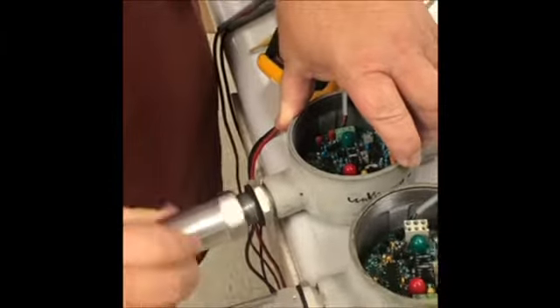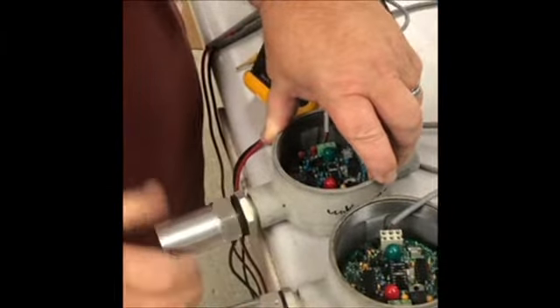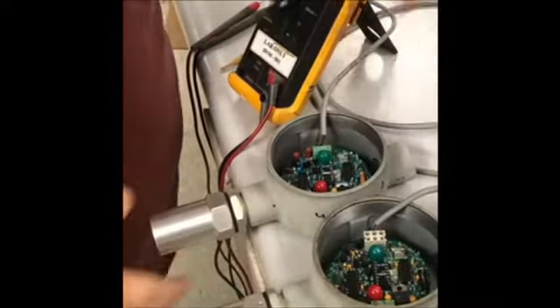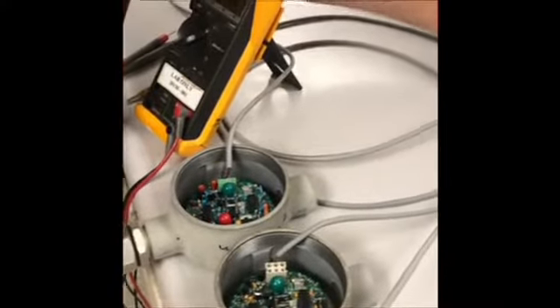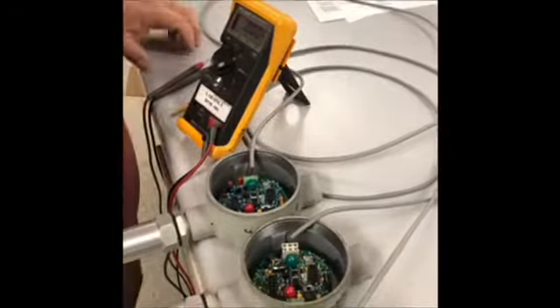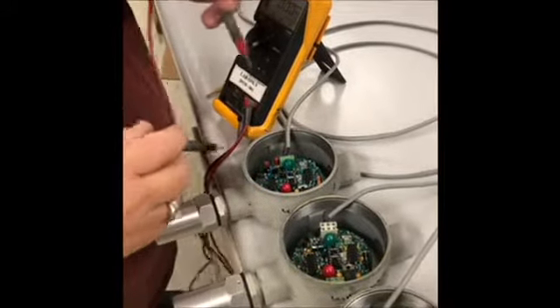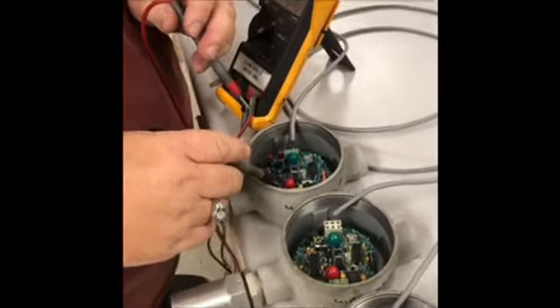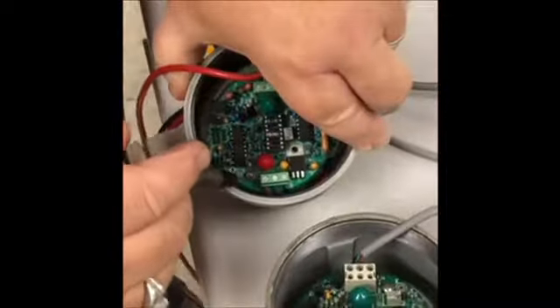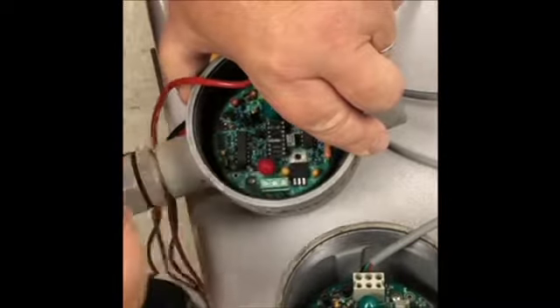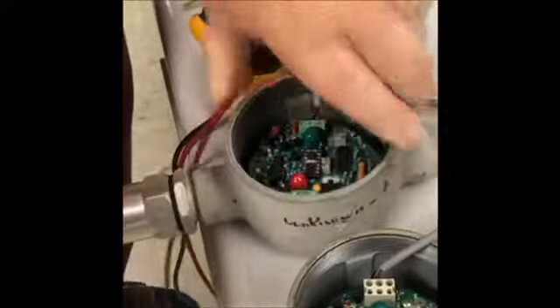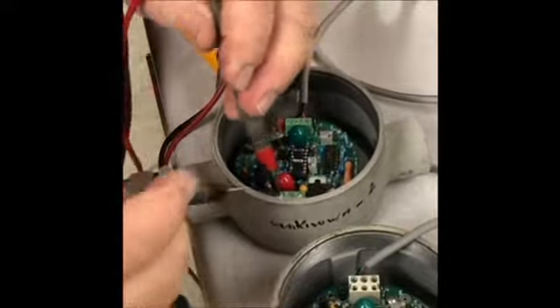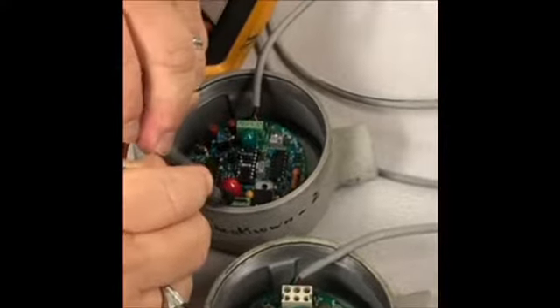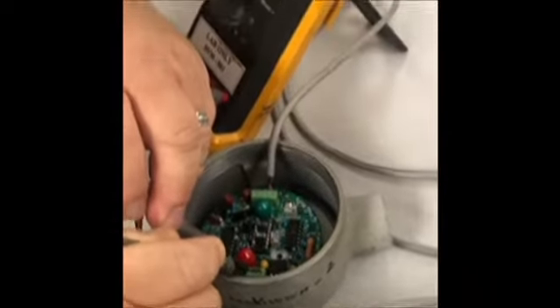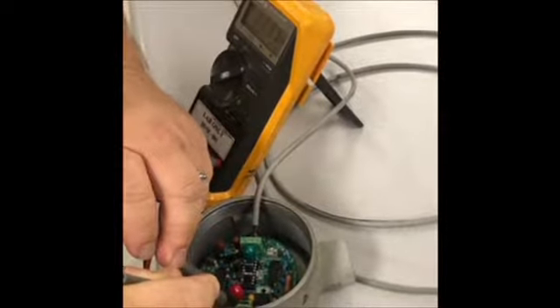Put the F44, the rain shield, back on. Reapply the power to the sensor. You can come over here to this terminal block. This terminal block is where you measure the heater voltage. These wires come from the sensor socket over here. You measure across pins 1 and 3 to see what the heater setting is. The heater setting on this one in this case is about 1.1 volts.